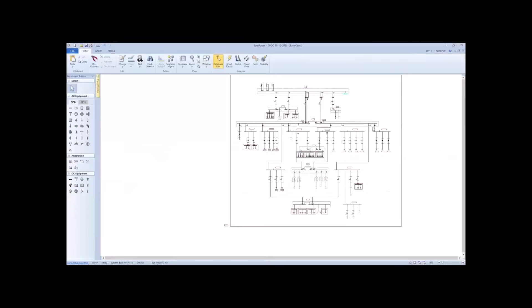So let's go to EasyPower. But first, let's look at the results we got from it - for instance, some TCCs, the curves of relays, breakers, transformers, power cables, and the one-line diagram. In EasyPower we got these curves, and in our report we included all of them as attachments to the final coordination study report. We also included all the relay settings - in the coordination study report we can export, using PDF, all the settings of the relays and breakers to include in our study. Okay, let's come back to EasyPower.